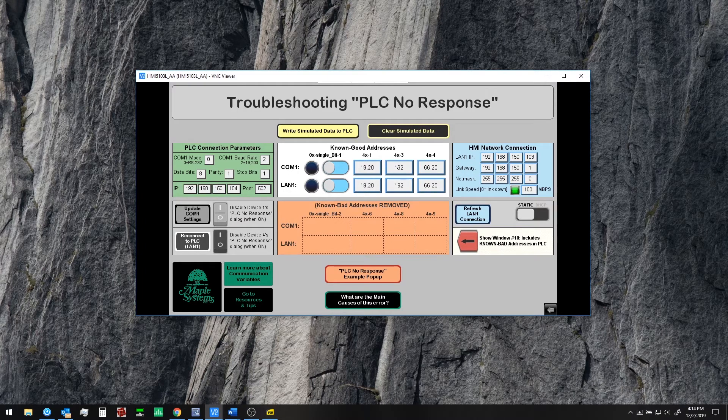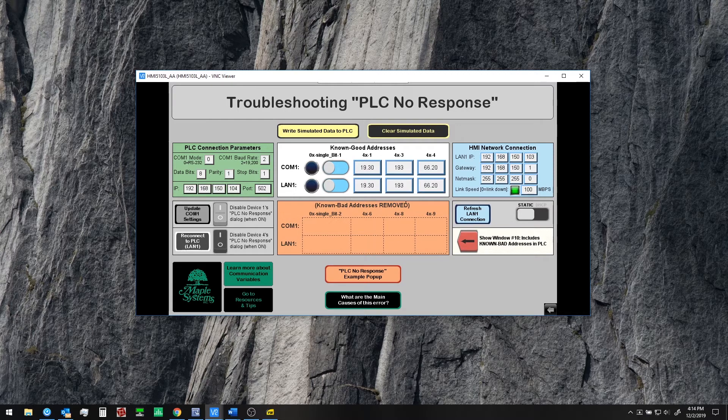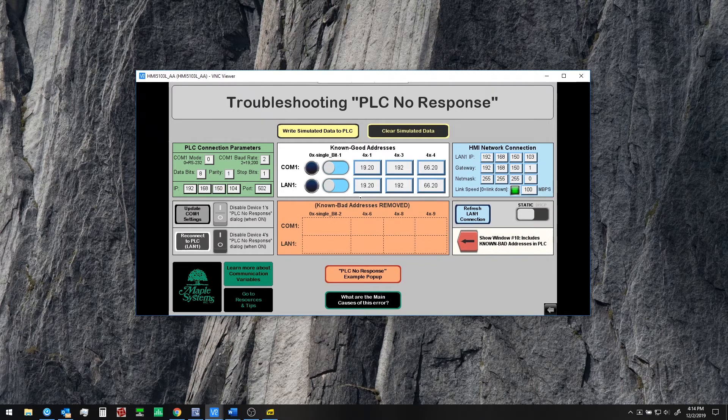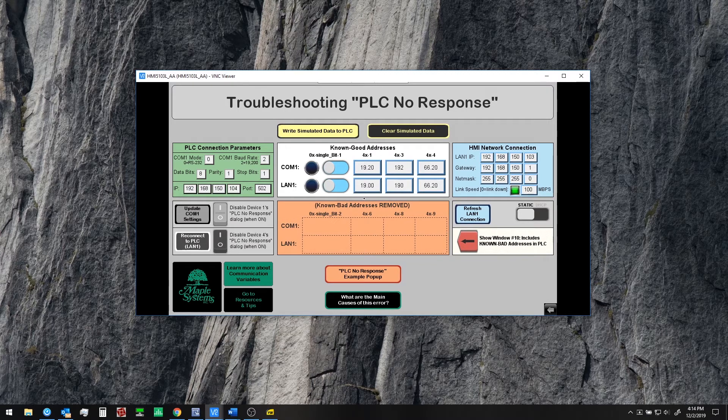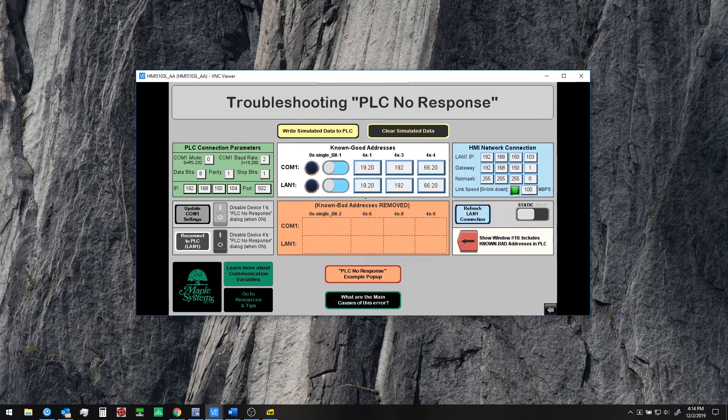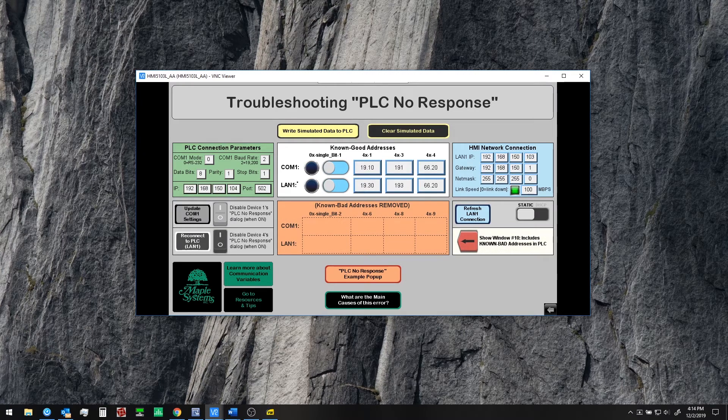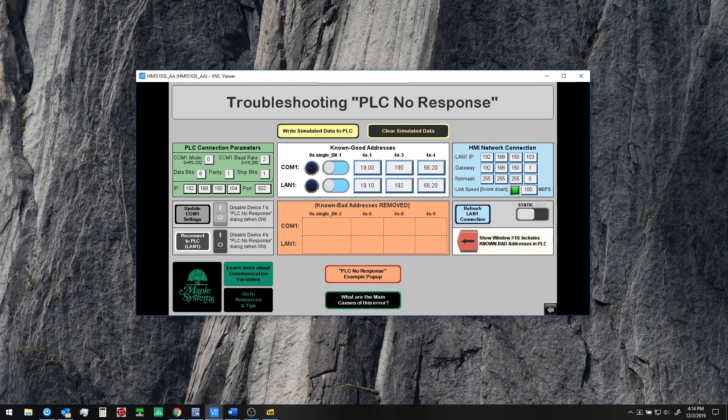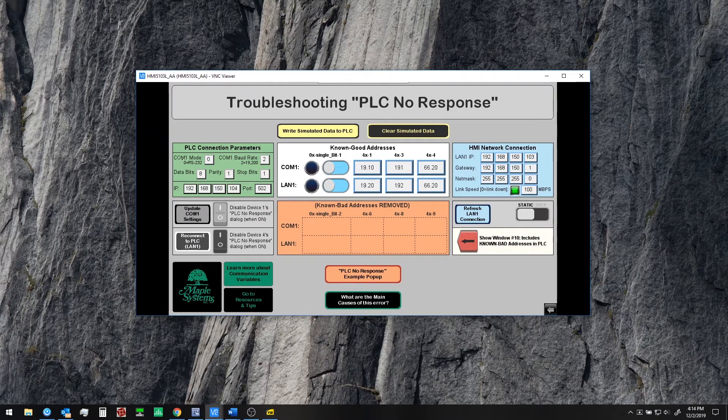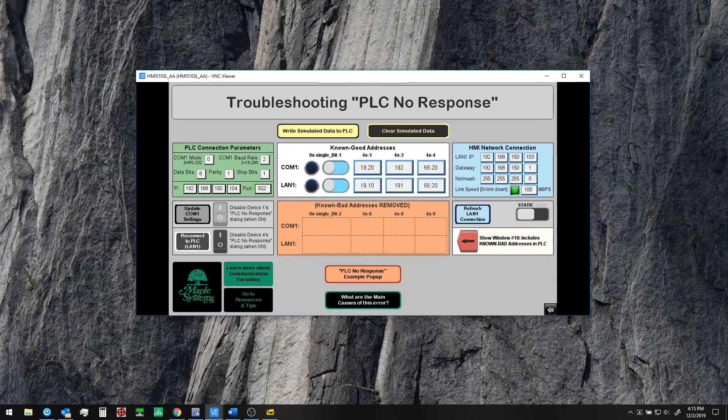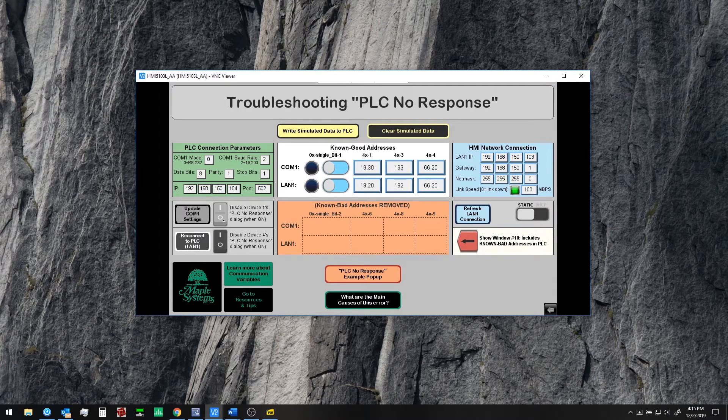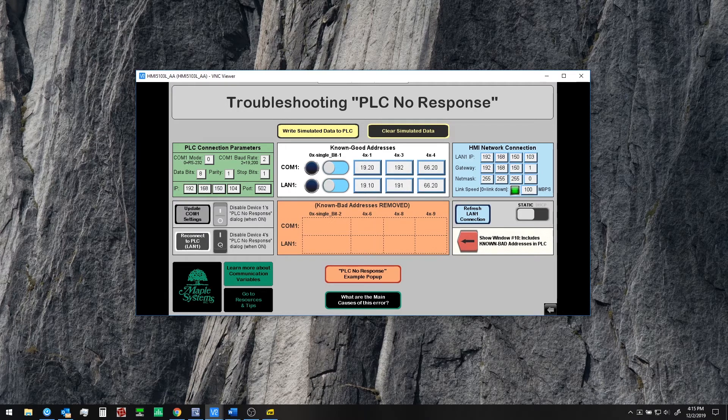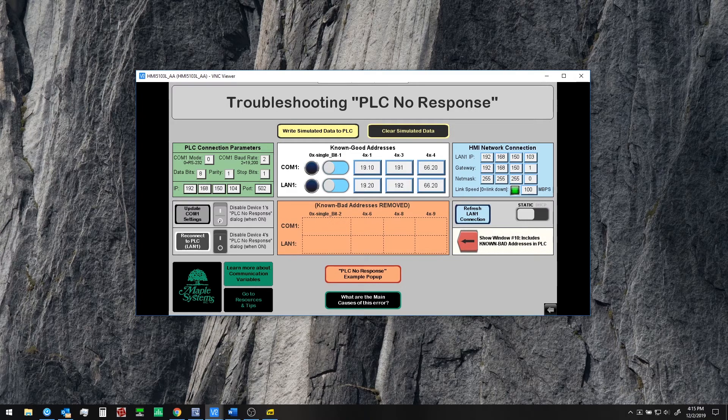So when we see that behavior we know generally that it's an addressing issue. Another thing that we can look at is the PLC connection parameters and how if we change the connection parameters here on COM1 or on LAN1 we will get a PLC no response message as well. We're going to show these dialogs now again.